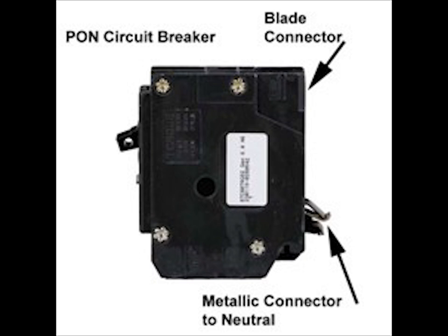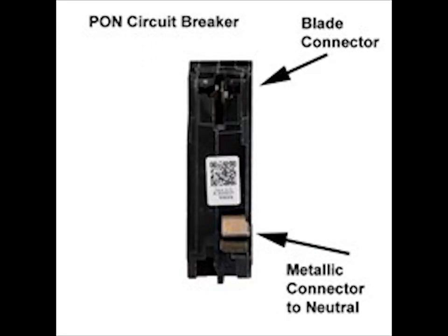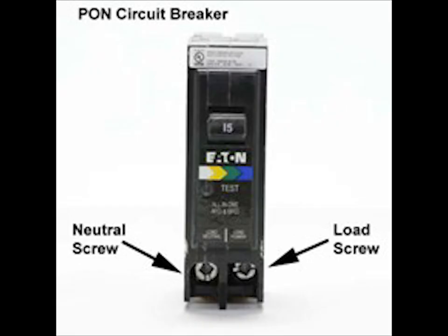Here is a ground fault interrupt and/or arc fault circuit breaker for a plug-on neutral load center. This circuit breaker has two metal connectors on the back. One is for the power connection, the other is for the neutral bar connection. The circuit breaker hooks into the load center with a metallic conducting hook. Two screws to attach wires to the breaker, load power for the black wire and neutral for the white wire.